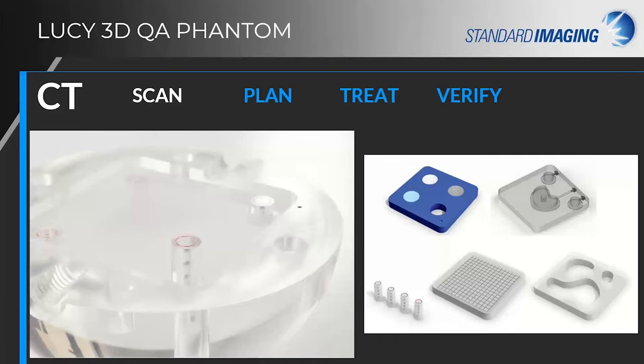It's very important, therefore, to perform a variety of QA tests on these imaging systems, especially since a lot of imaging systems are not necessarily at the treatment facility. And you may not be doing the day-to-day QA, but you're going to want to do a periodic QA to make sure that stereotactic treatment chain is as tight to those tight tolerances as possible.